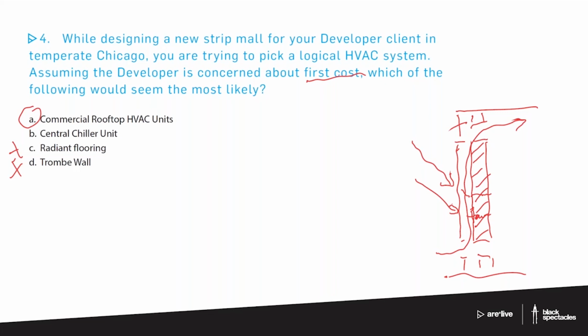The reason for that is the rooftop units have a fairly short timeline. If you imagine, where would you want to be if you were in Chicago? If you were an HVAC unit, would you want to be sitting up on the roof in Chicago, or would you rather be in a nice, controlled basement space? Well, the chiller is likely to be in that nice controlled basement space. That rooftop unit is going to be in the sleet, the snow, the hot sun, the UV rays. It's going to have all those troubles, but it's an off-the-shelf piece.